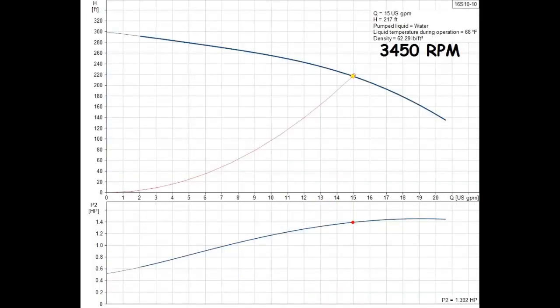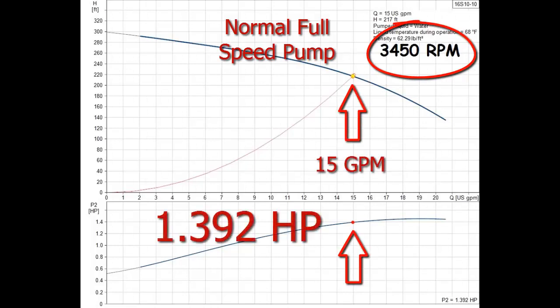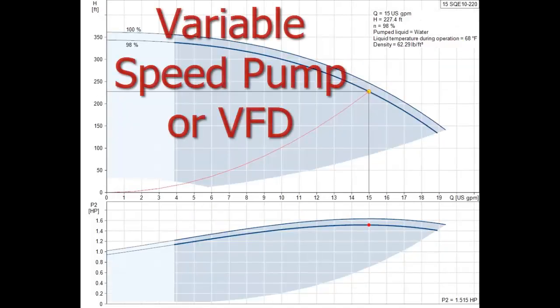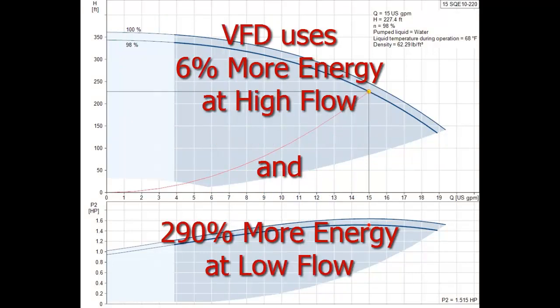Then if you compare a normal full speed pump producing 15 gallons per minute at 1.392 horsepower to the variable speed pump at 1.515 horsepower, the variable speed pump is using 6% more power per gallon produced at high flow rates. Even with state of the art technology, permanent magnet motors and all that, variable speed pumps always use more energy per gallon, not less.